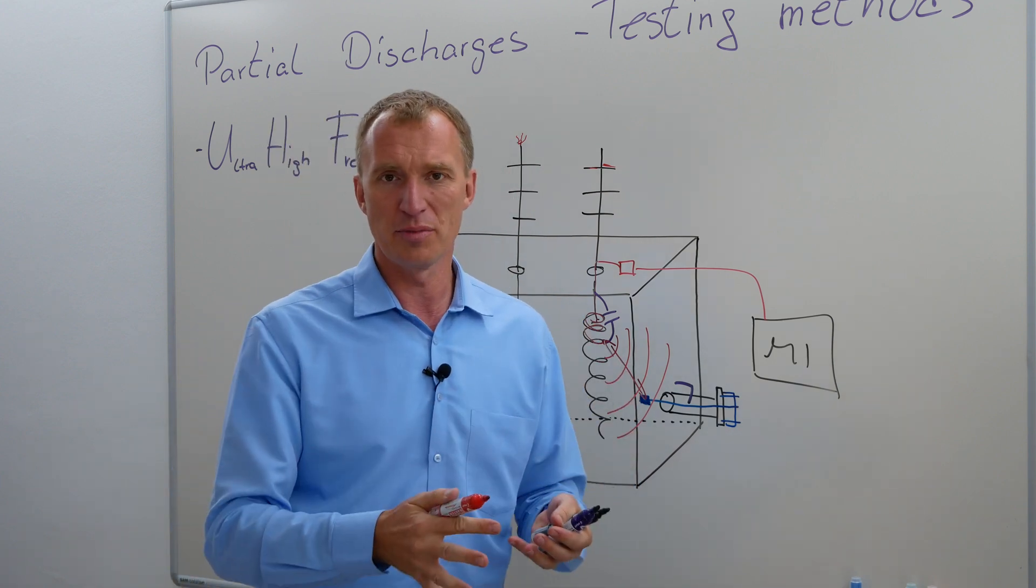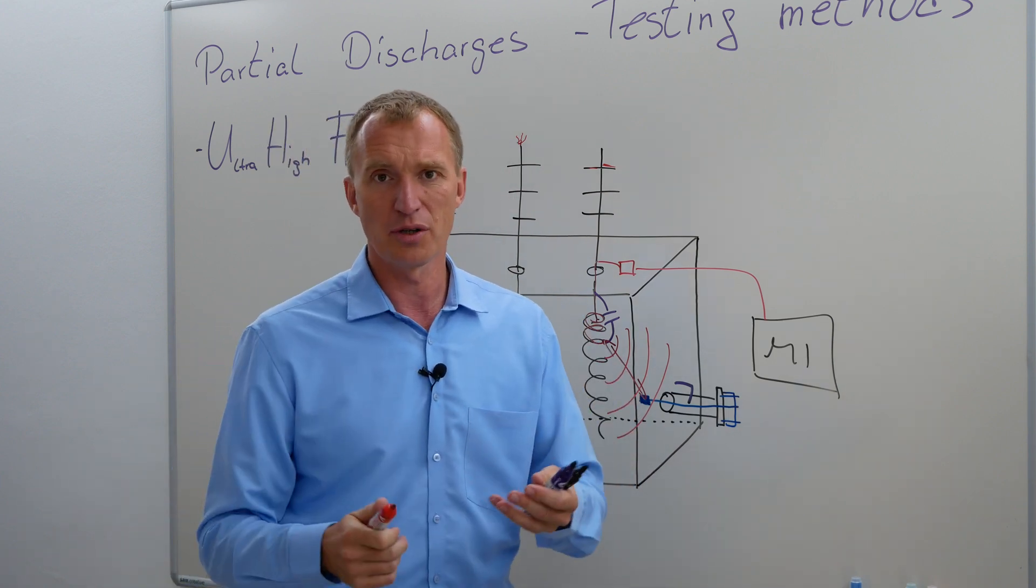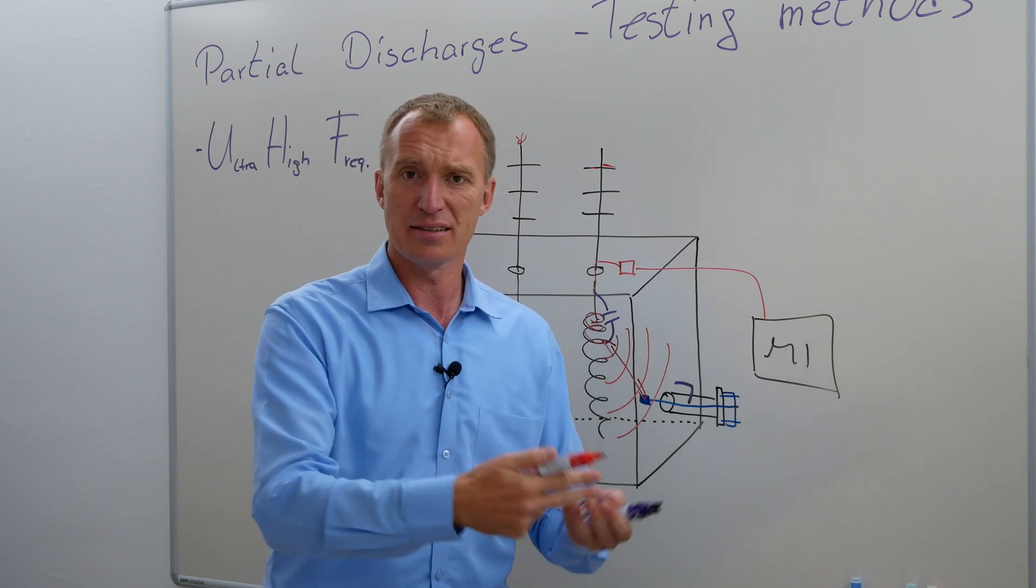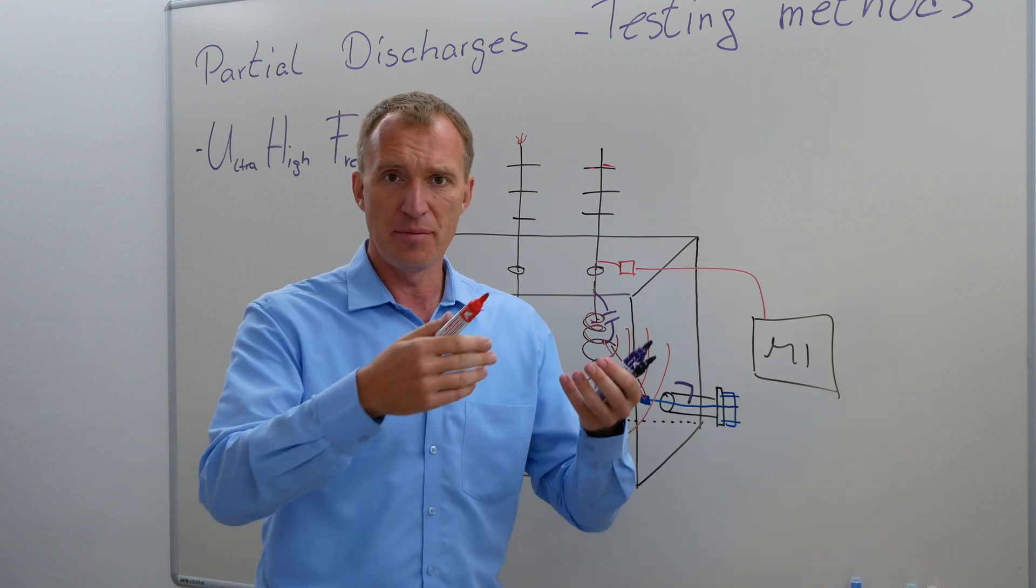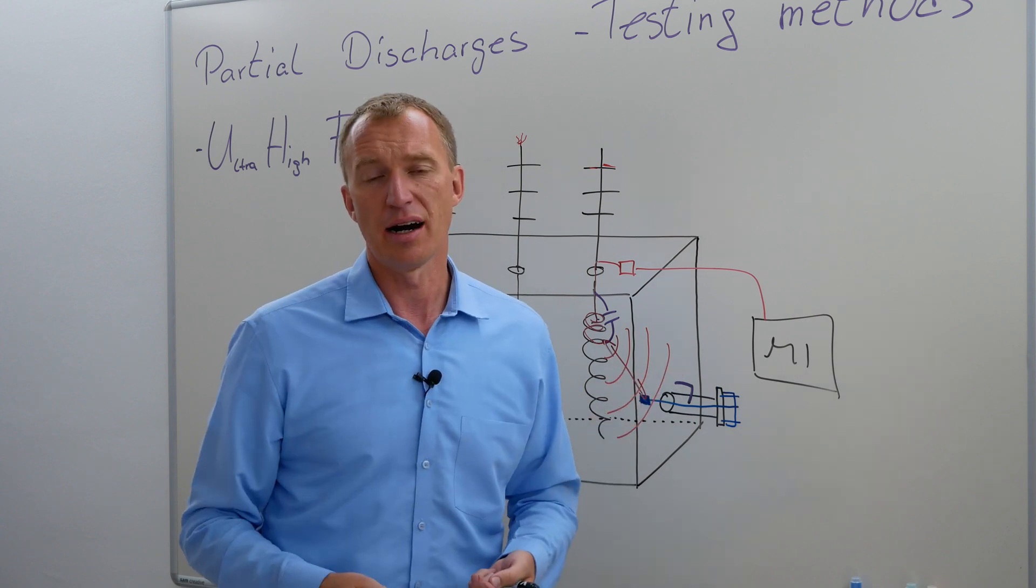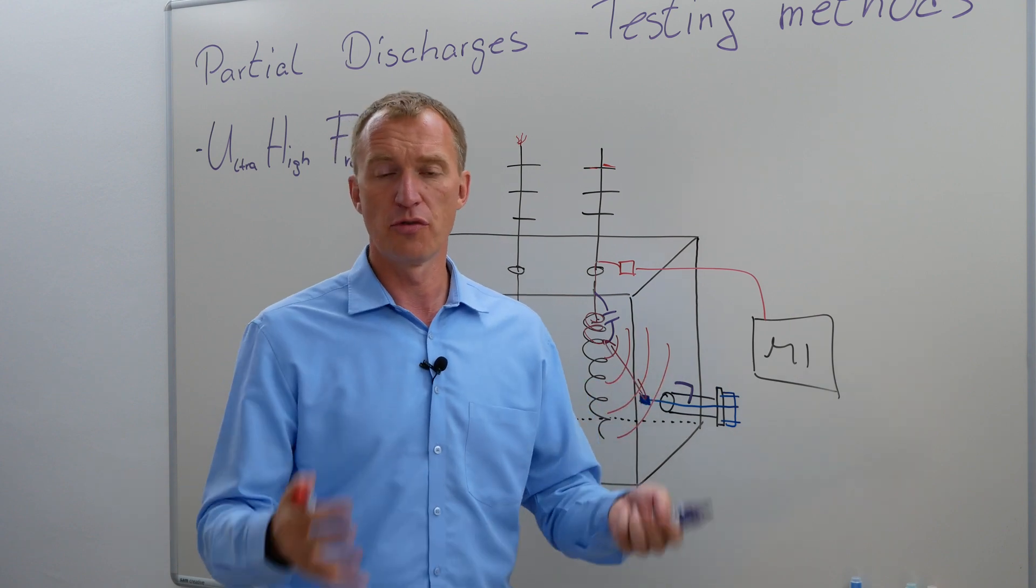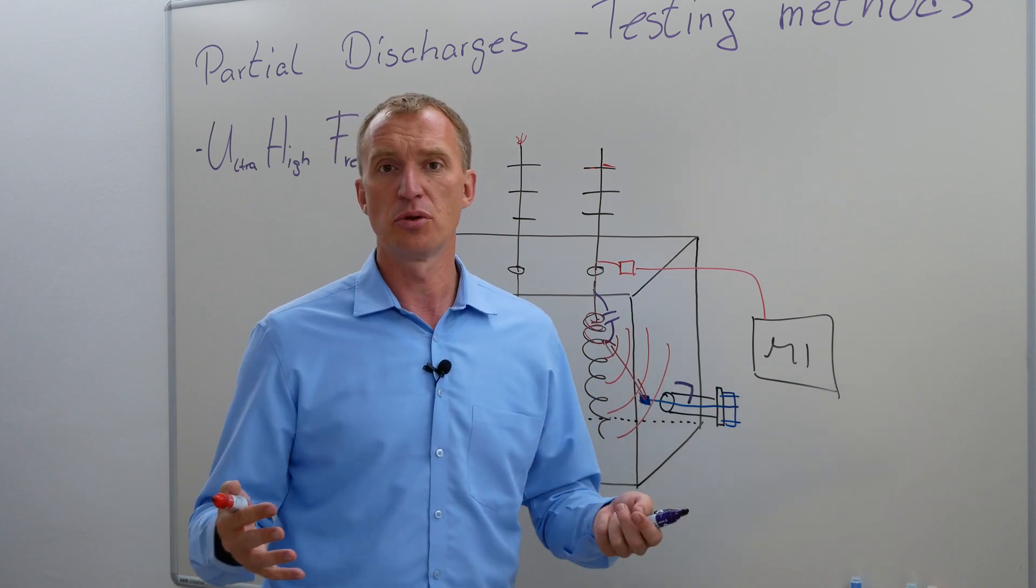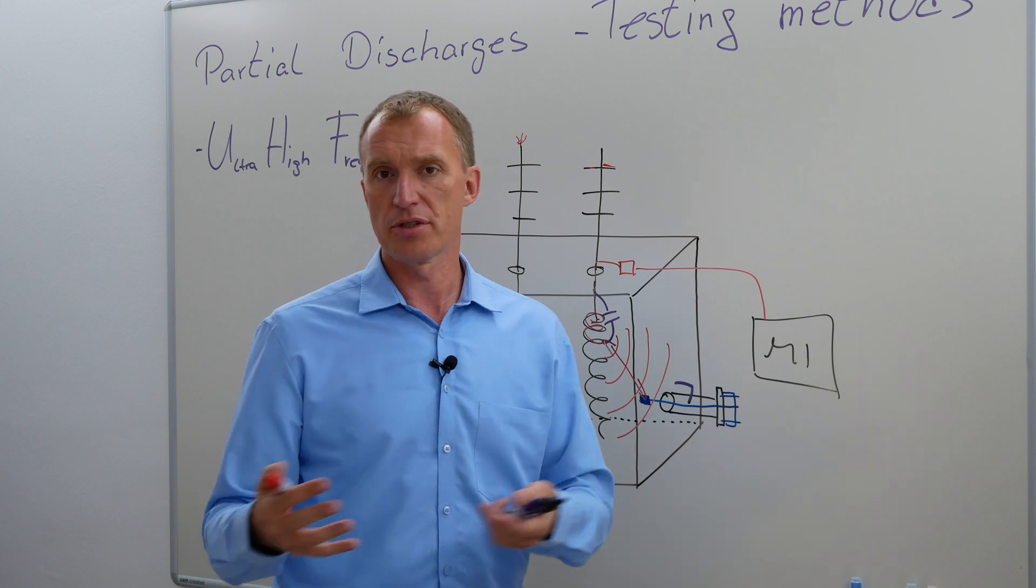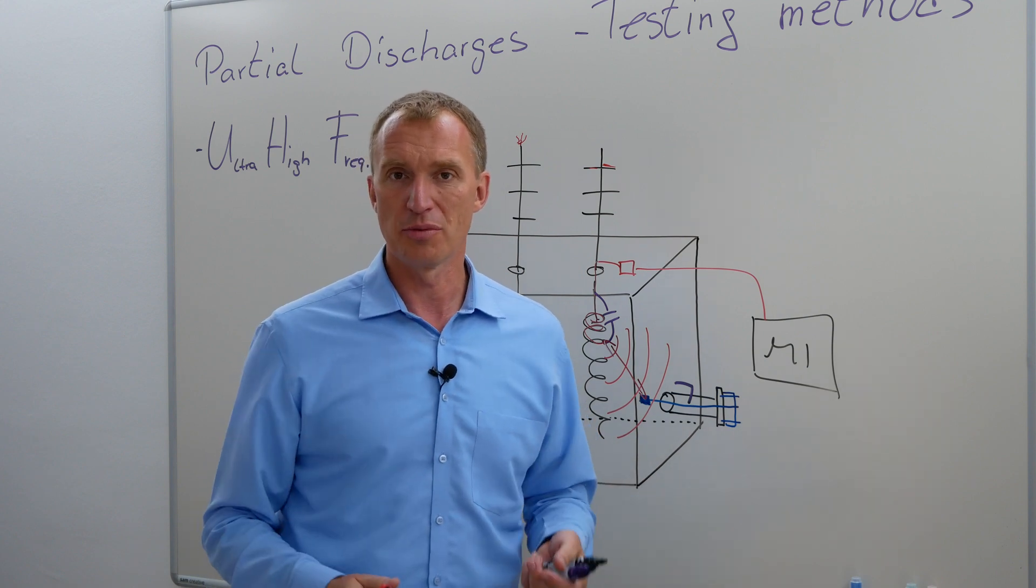So UHF measurement or UHF detection, however you want to call it, allows you to get inside a high-voltage device and be able to get the ultra-high frequency content of a partial discharge, and this helps you to make an evaluation about the state of our high-voltage device.